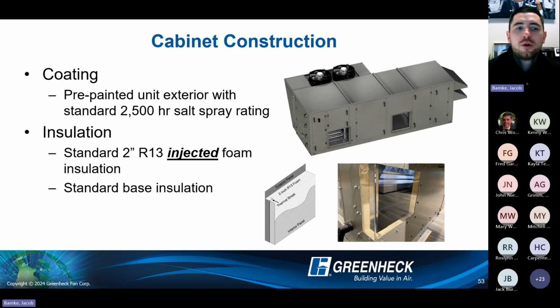As far as construction goes, this is really where you start to see some differentiation between your traditional rooftop equipment and then a true high percentage outside air unit. Coating, want to make sure that this unit lasts as long as possible. Our coating is a standard kind of pre-painted panel. We call it a permatector. It's this concrete gray color, but it carries a standard 2,500 hour salt spray rating.